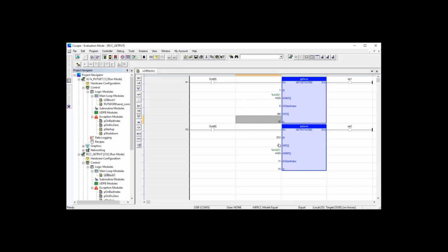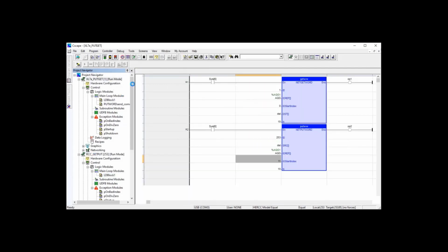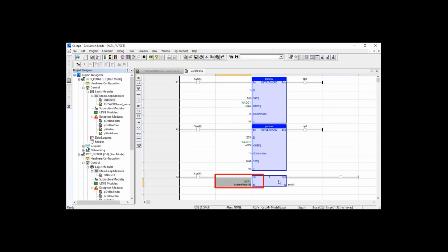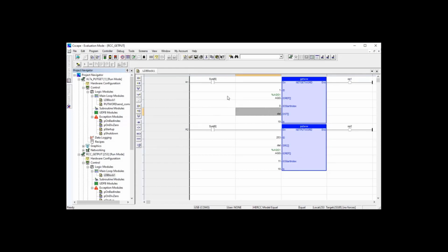The RCC of ID 253 is then transmitting this same data back to the network with the IO start index as 11, which is being received at the XL7E. This program is already downloaded and running in the RCC. In the XL7E, I'm transmitting the data system registers SR44, which is the real-time clock seconds value, to source variable index 0, which we can get in the RCC destination address.